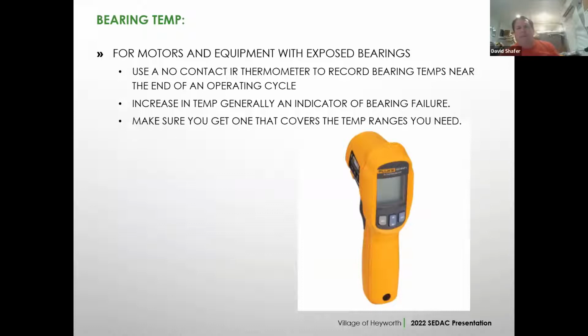If you have motors or equipment with exposed bearings or end bearings, checking the bearing temperature with a non-contact thermometer near the end of the operating cycle can give you an indication of the potential for bearing failure. The only thing I'd say is make sure you get a thermometer that covers the temperature range you're looking for. If you're stealing the one from the medicine cabinet for junior, it's probably not going to register a temperature high enough to do you any good. Get something that covers up into a couple hundred degrees. That way you can also use it for checking asphalt temperature when you're paving roads and doing other things as well.